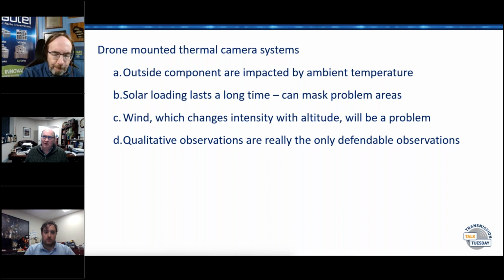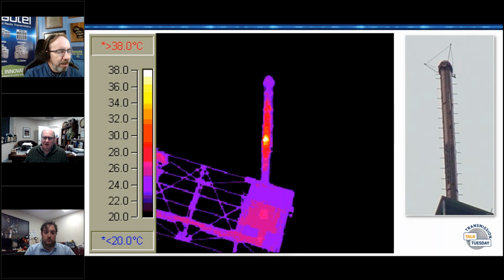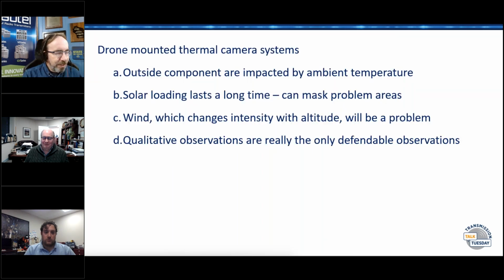It's interesting, we'll cover it elsewhere, but mechanical stress can show up thermally. We did a recent case where we saw that one leg of the tower was warmer, and there was no electricity in it, but it was just flat hotter because of the way the tower was stressed. We mentioned it to a tower climber, and they checked it out and did some guy wire retensioning. So it's silly stuff you'll see like that.